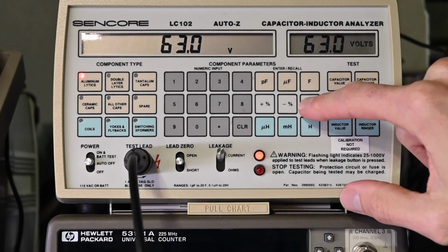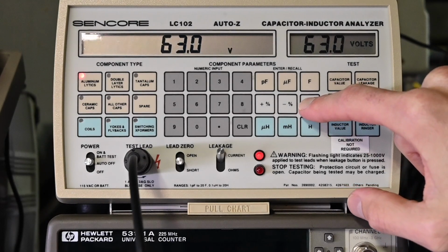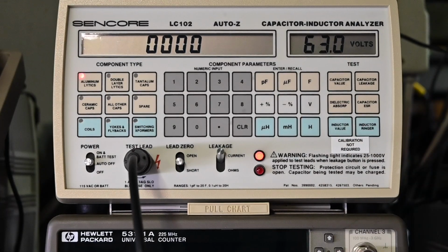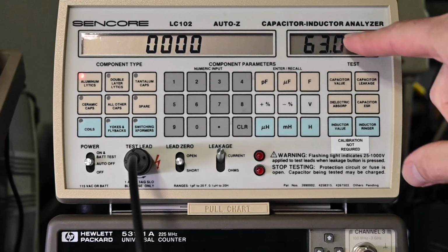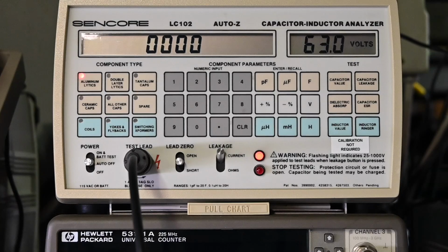And then the voltage, 63 volts, and that's for the leakage test. And again, this capacitor is rated 63 volts maximum. You can see that value over here as well. And that's really where this meter shines, is that ability to do the leakage test and put that voltage onto the capacitor and actually test it under actual voltage conditions, where, as you saw with the other meters, they cannot test for leakage. And you'll see in just a moment how important that test is.